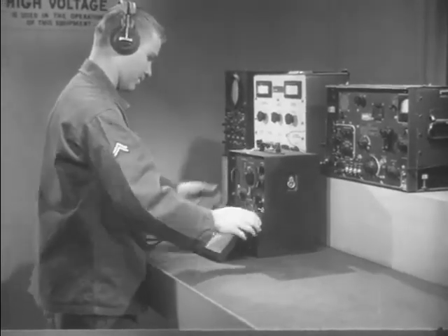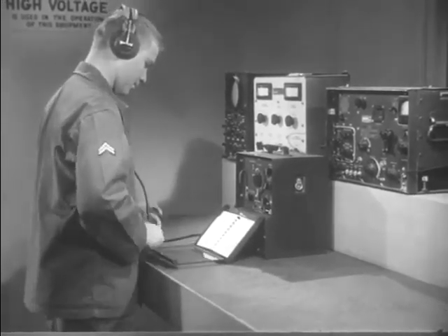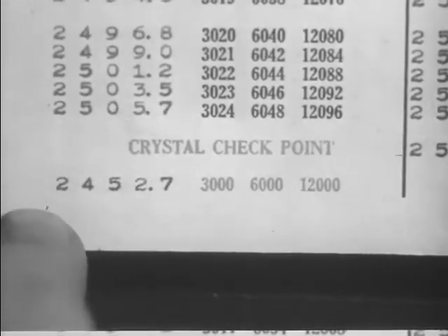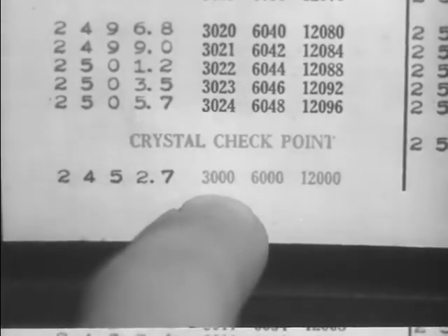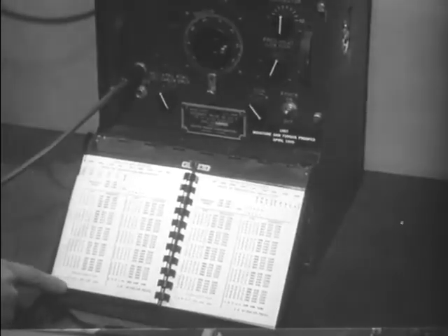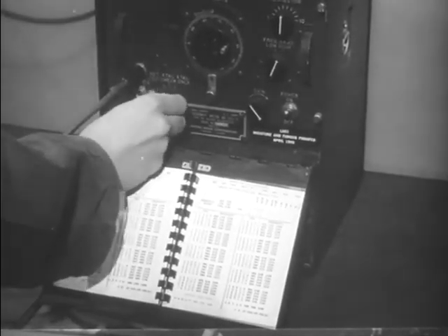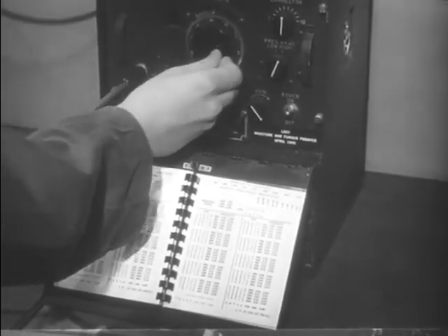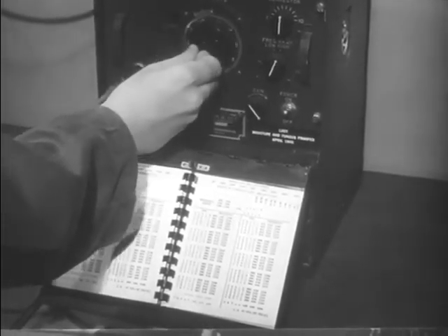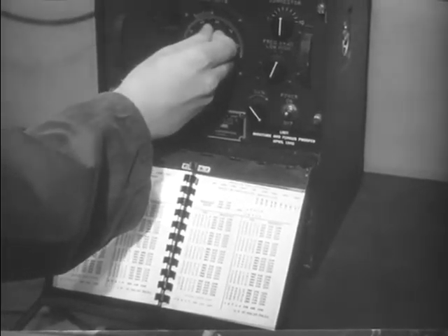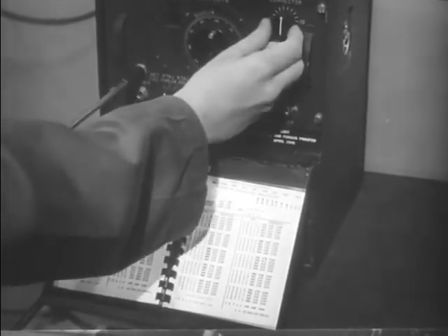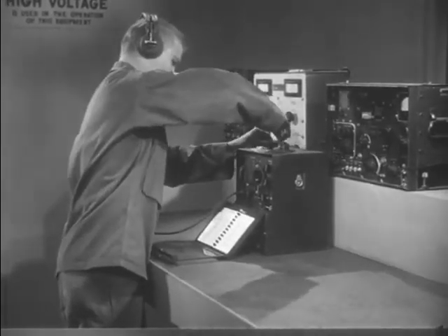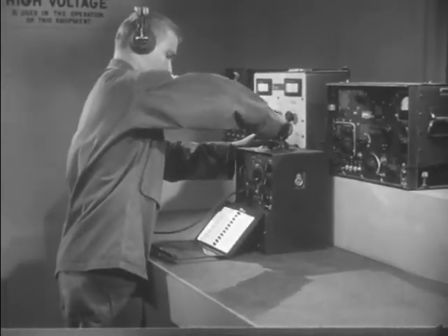The frequency meter or wave meter is not used as other signal generators, but it is closely allied. It is a precision instrument, and a calibration chart is included with each set to ensure accuracy in tuning. This set is used for the generation and measurement of radio frequency signals to an extremely accurate degree. It serves also as a radio frequency standard in the tuning and calibration of radio transmitters and receivers and signal generators. The frequency meter might be called a signal generator to test signal generators.